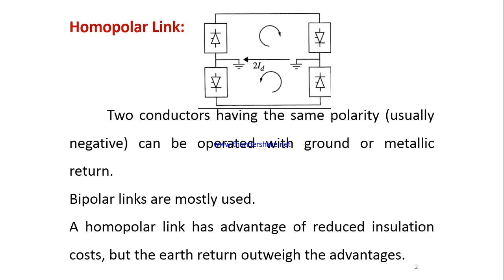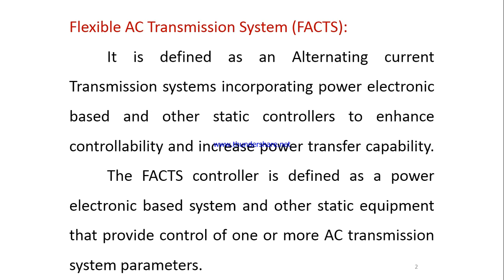While considering the homopolar link, the two conductors have the same polarity, and this can be operated with ground or metallic return. Bipolar links are mostly used, and a homopolar link has the advantage of reduced insulation cost, but the earth return outweighs the advantage. While considering FACTS, it is defined as an alternating current transmission system incorporating power electronic based and other static controllers in order to enhance the controllability and increase the power transfer capability. A FACTS controller is defined as a power electronic based system and other static equipment that provide control of one or more AC transmission system parameters.